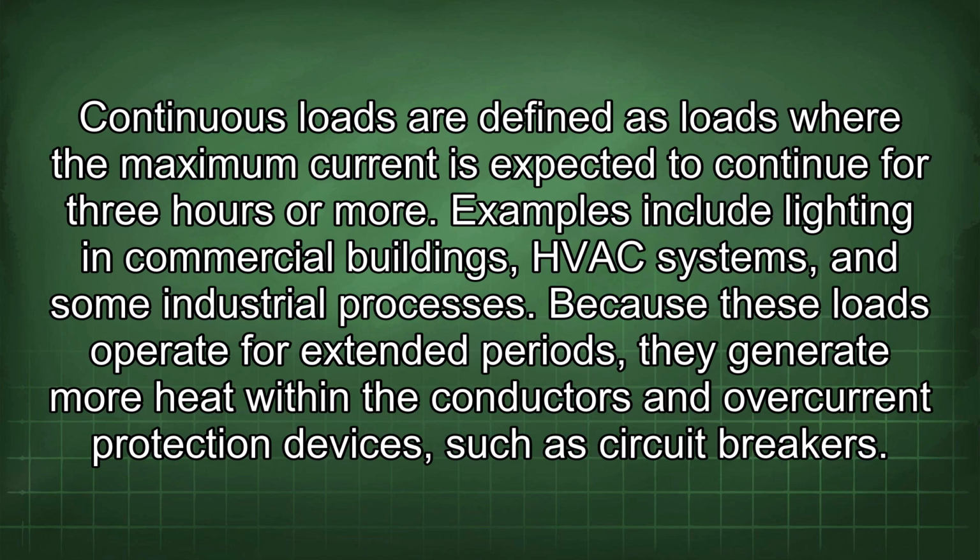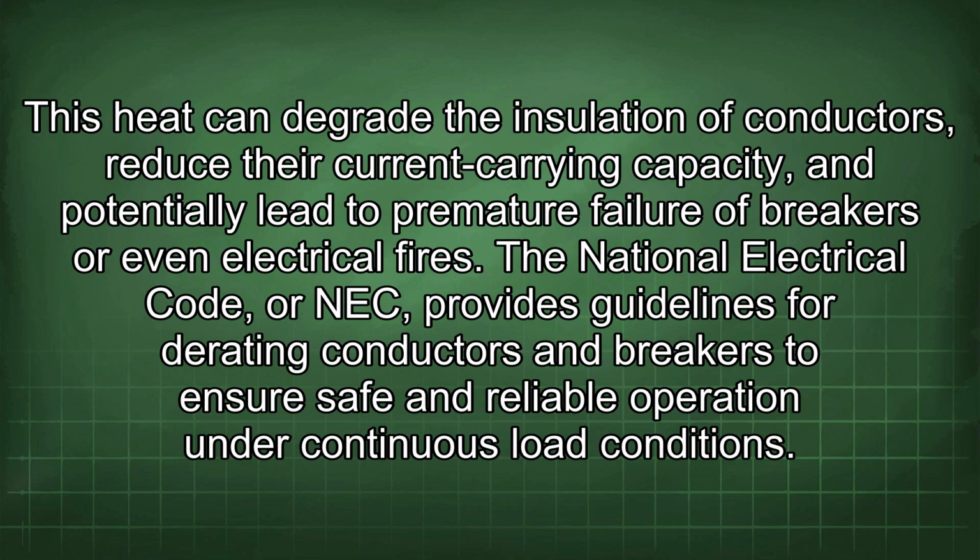Because these loads operate for extended periods, they generate more heat within the conductors and overcurrent protection devices, such as circuit breakers. This heat can degrade the insulation of conductors, reduce their current carrying capacity, and potentially lead to premature failure of breakers or even electrical fires.